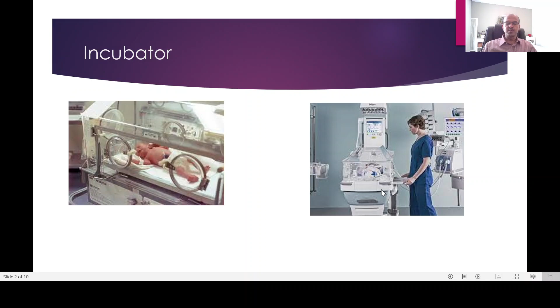The main idea of the incubator is to give an enclosed space where the temperature is regulated according to the baby's needs. You also have the option to add water vapor pressure in the incubator. That's called humidity. You can keep a higher humidity so the baby does not lose water vapor from the thin skin. This will help the temperature support. You might have a temperature probe on the skin, and the nurses do monitor and adjust the temperature accordingly.